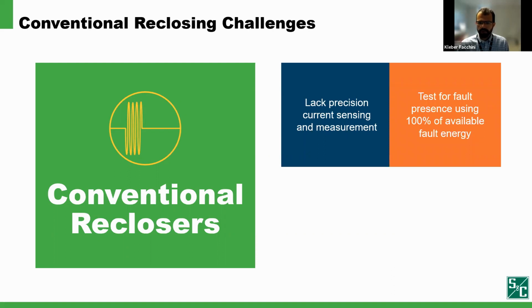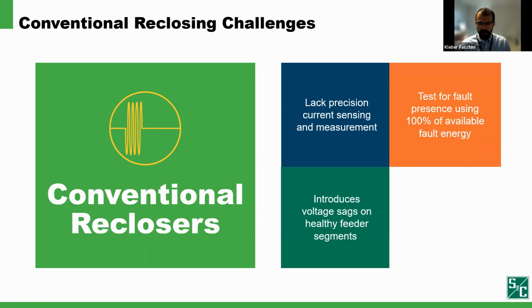Conventional reclosers use 100% of their available fault energy to test for continued fault presence, which repeatedly stresses the power system upstream of the fault. Reclosing reintroduces harmful voltage sags for customers on healthy feeder segments upstream of the faulted feeder segment, which can adversely affect electronic equipment and distributed energy resources, especially as more DERs are introduced and installed in the feeders in our system.